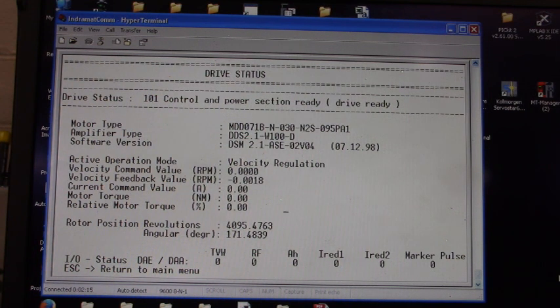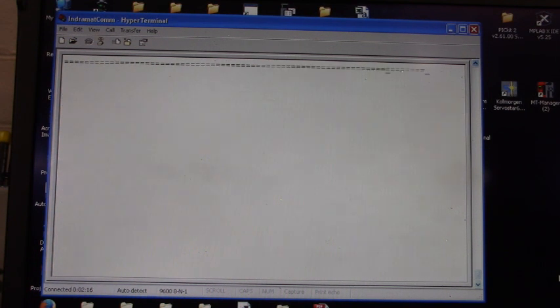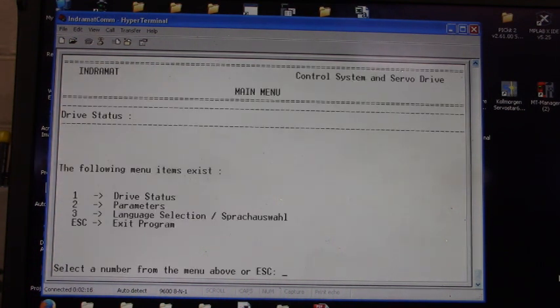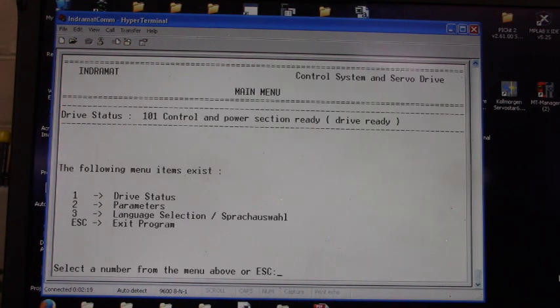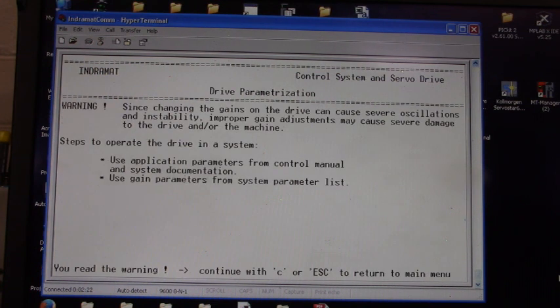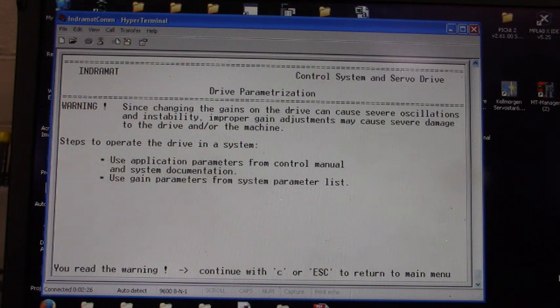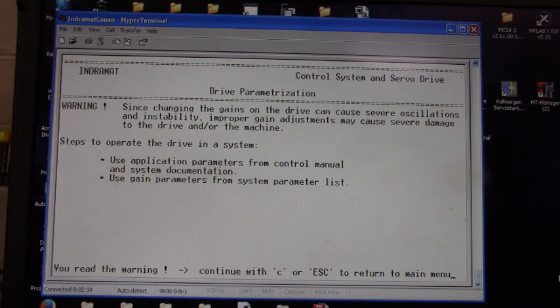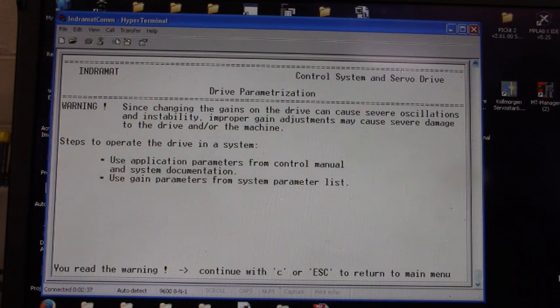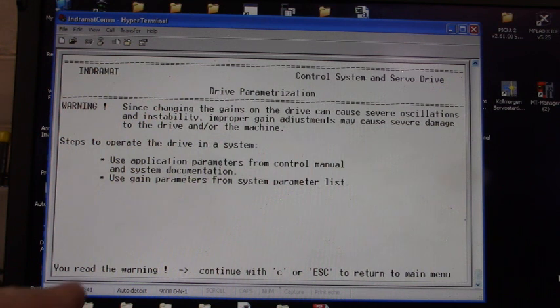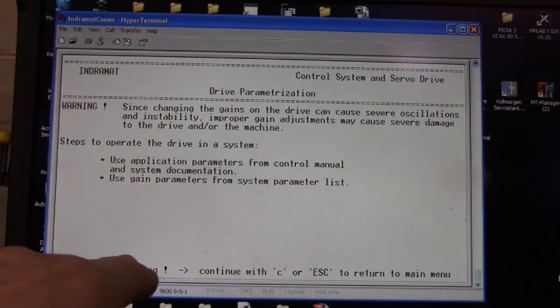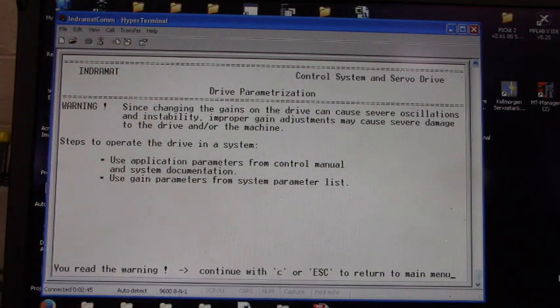Let's press the ESC key and we'll go to drive parameters. Now they're telling us to be careful, since changing the gains of the drive can cause severe oscillations and instability. Improper gain adjustments may cause severe damage to the drive and/or the machine. So we read the warning, we're going to press C to continue.